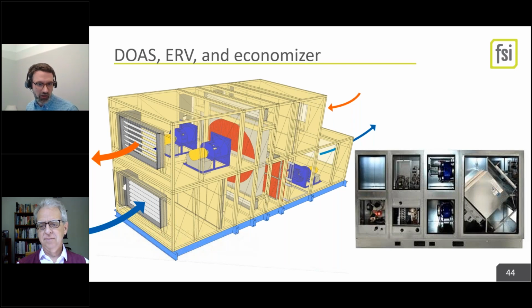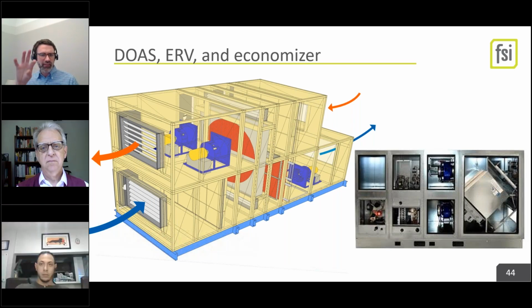So we get this question all the time, what about the air leakage, right? Because there's got to be some air leakage. And 62.1 has handled this. They have air classifications, and I'm not going to get too deep into this. But for things like restroom exhaust and just general purpose relief return exhaust, you're allowed to have 10% leakage to the supply airstream. And that air is primarily an odor concern. There's no real toxic health hazard concern. So you're allowed to have a minor amount of air leakage. That's the maximum, right? Hopefully you get less. And there's little blade seals that keep too much air, so it's really only the air in the core that gets leaked around.